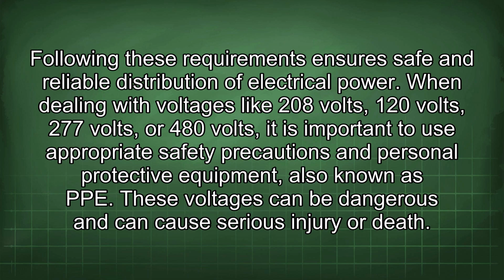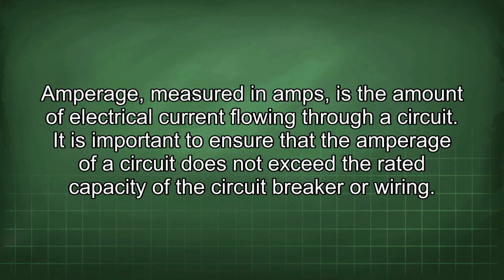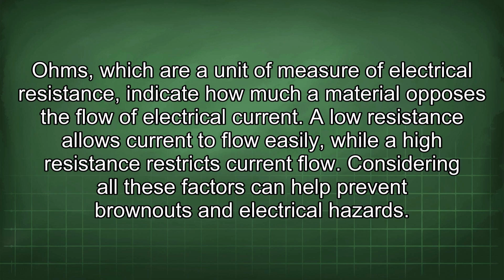When dealing with voltages like 208 volts, 120 volts, 277 volts, or 480 volts, it is important to use appropriate safety precautions and personal protective equipment, also known as PPE. These voltages can be dangerous and can cause serious injury or death. Amperage, measured in amps, is the amount of electrical current flowing through a circuit. It is important to ensure that the amperage of a circuit does not exceed the rated capacity of the circuit breaker or wiring. Ohms, which are a unit of measure of electrical resistance, indicate how much a material opposes the flow of electrical current. A low resistance allows current to flow easily, while a high resistance restricts current flow. Considering all these factors can help prevent brownouts and electrical hazards.